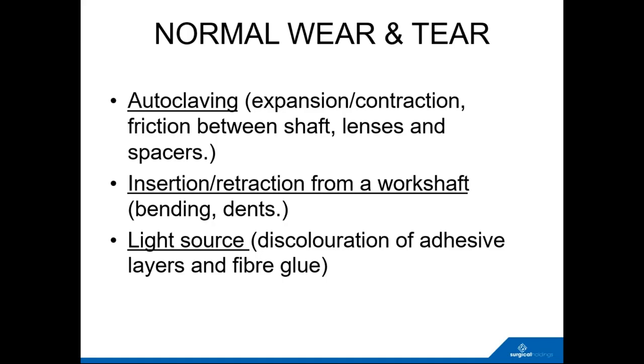There's normal wear and tear damage. Autoclaves are not wonderful things for fragile instruments. There's obviously expansion and contraction due to the heat, so there's friction, the lenses move, there's spacers, in fact in some larger scopes there's even springs to counteract the expansion, to ensure the expansion contraction. When it contracts after the autoclave, everything goes back into place, but that can cause damage after a while.